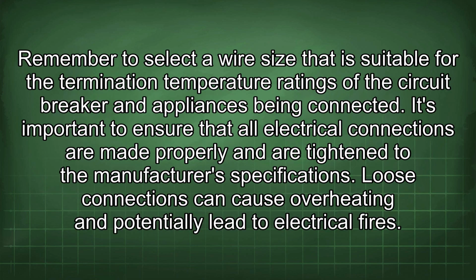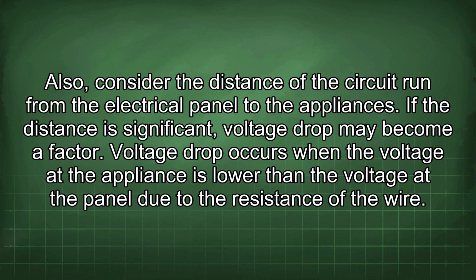Remember to select a wire size that is suitable for the termination temperature ratings of the circuit breaker and appliances being connected. It's important to ensure that all electrical connections are made properly and are tightened to the manufacturer's specifications. Loose connections can cause overheating and potentially lead to electrical fires. Also, consider the distance of the circuit run from the electrical panel to the appliances.